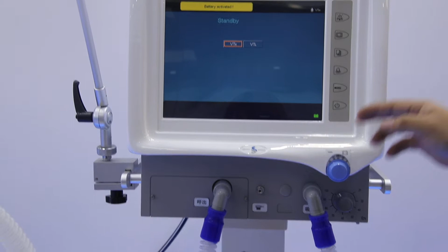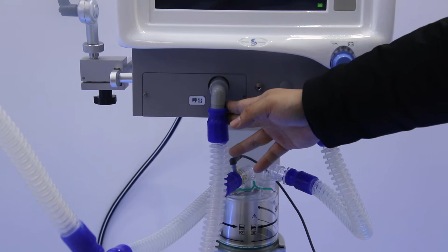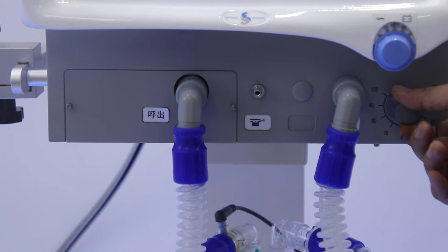And here you can see, for this machine we have a total of 4 ports. The first one here is the expiration port, and this one is for the nebulizer. Once we need to use this function, we need to connect with a small pipe. And this one is reserved. Later if the customer needs EtCO2, then we will make this port. And the fourth port here is for the inspiration port. And this rotate button is for adjusting the oxygen concentration from 21% to 100%.